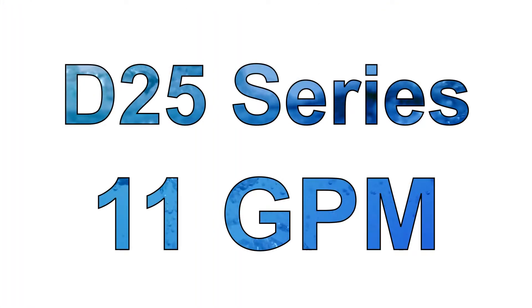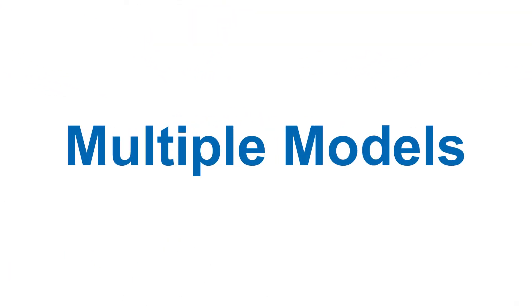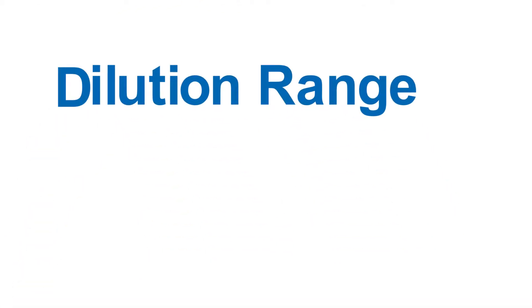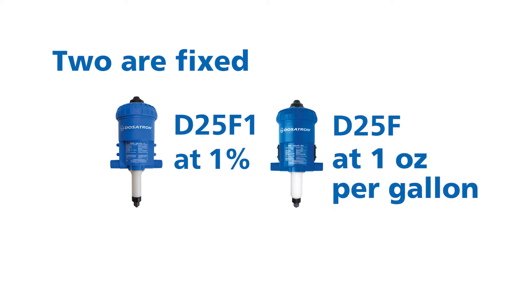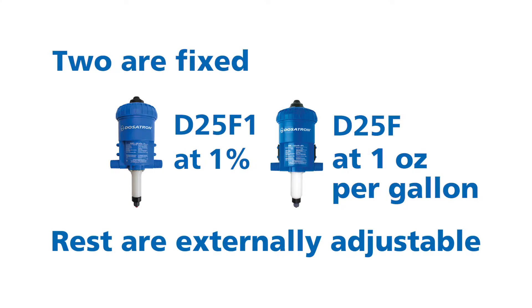The D25 series has a maximum water flow of 11 gallons per minute. Multiple models in this series provide a dilution range from 1 to 1500 to 1 to 10. Two of them are fixed, one at 1% and the other at 1 ounce per gallon, and the rest are externally adjustable.